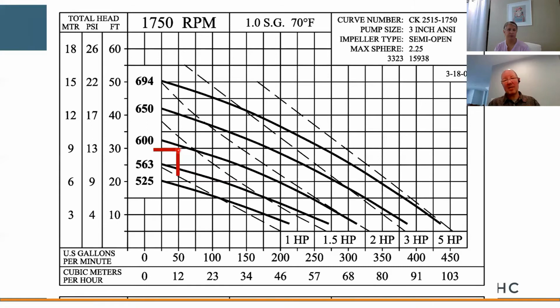Now, most HVAC engineers, most guys who do a lot of closed loop heating systems, are used to non-overloading motors. Which means we take the 6-inch impeller line, which is where we would operate, and we'd get all the way to the end down here without crossing a horsepower line. And we're really close here with 2 horse to be non-overloading. But let's just consider 2 horse non-overloading. Most plumbing engineers say, hey, I only need 30 feet of head. I'm going to select this pump based on duty point at 1.5 horse.